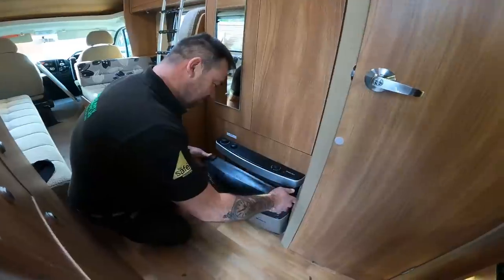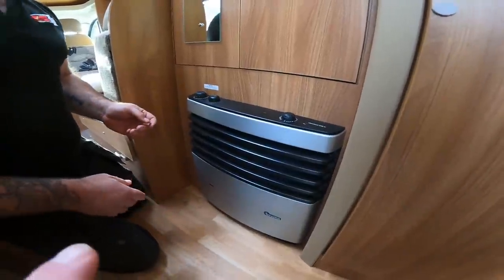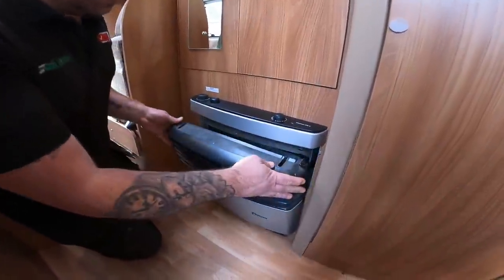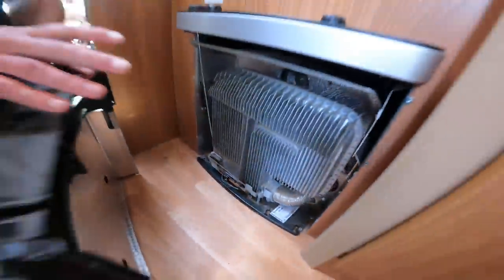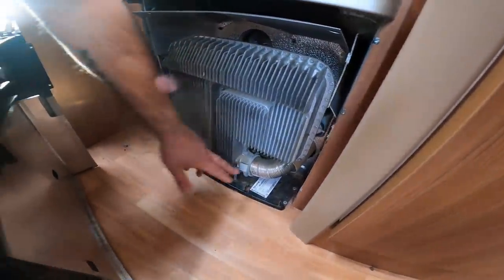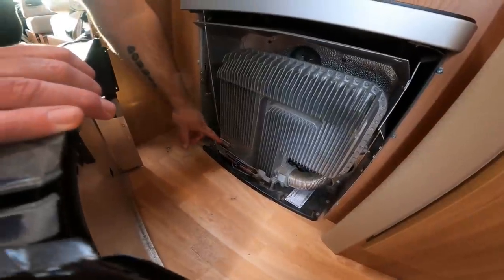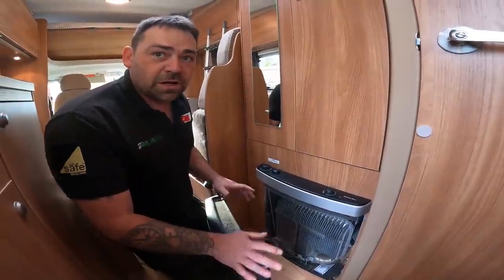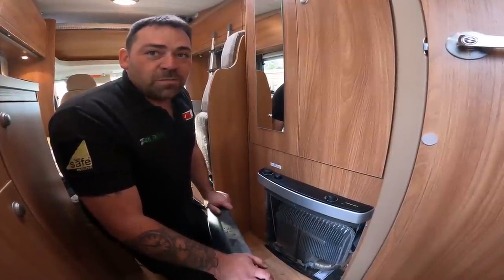Can we show people how to take the fire front off? Now, why would you want to take this off? If I was doing a service, I'd take this off — let me turn that fire off otherwise I'll burn my fingers again. This one has got two clips just on the inside there and it just lifts off — the actual fire sits on these little nips. For service I'd be cleaning behind it, getting the debris off, checking the flue connections, checking all the thermal bulbs, and making sure the sight glasses are all intact.